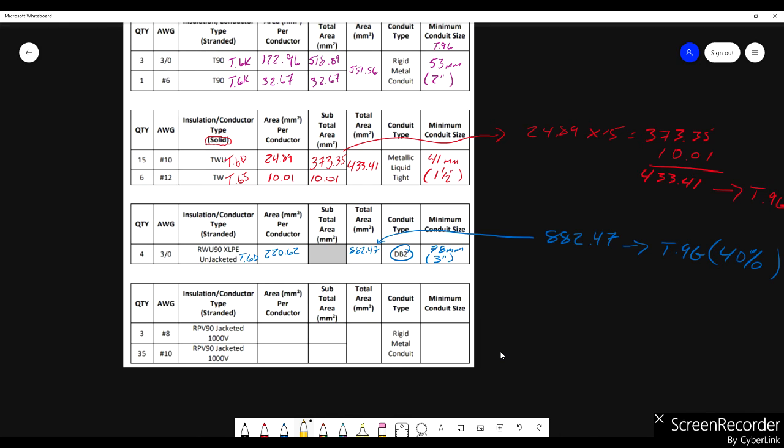That's fine per area. So first off, the table that we're going to look at for this one would be table 6H. So I don't reference this very often. I personally have not done solar panel wiring, but that's where you'd look. That's where you'd find this conductor, that insulation. Okay, 6H. So you go to table 6H for number 8, 3 of them.